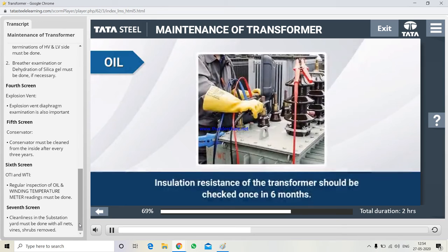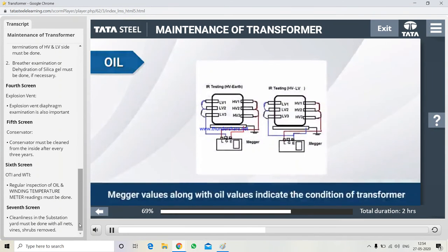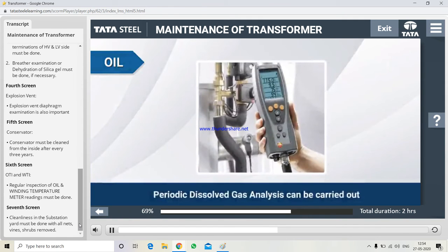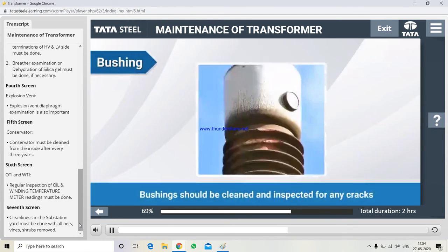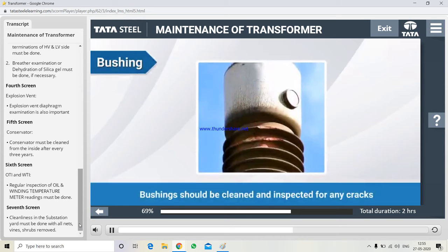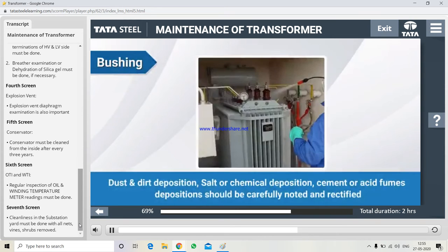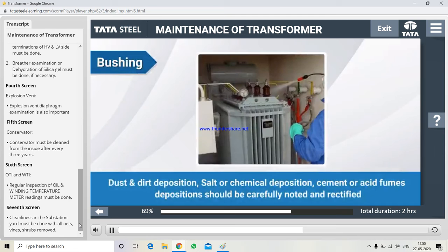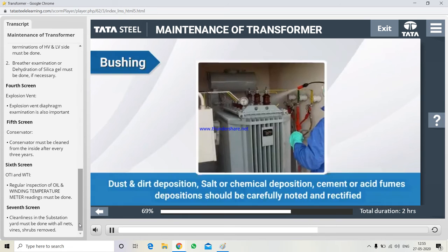6. Insulation resistance of the transformer should be checked once in 6 months. 7. Megger values along with oil values indicate the condition of the transformer. 8. Periodic dissolved gas analysis can be carried out. Bushings. 1. Bushings should be cleaned and inspected for any cracks. 2. Dust and dirt deposition, salt or chemical deposition, cement or acid fumes depositions should be carefully noted and rectified.